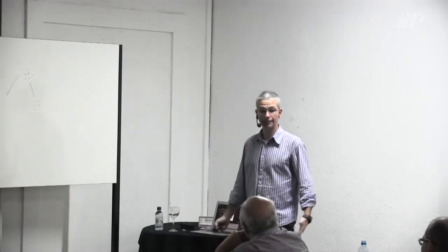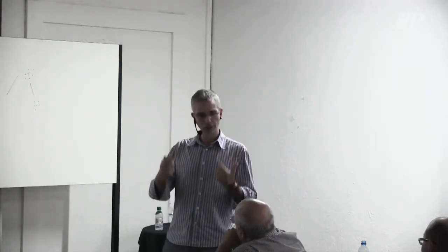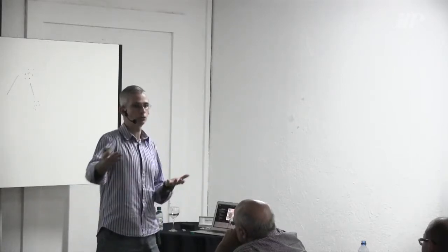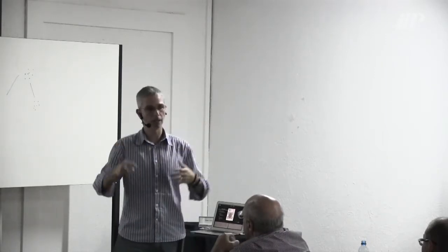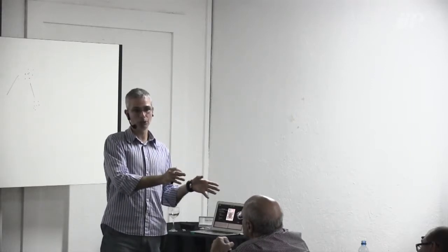Right. Well, depending on how you encode phase, 1.5 Tesla is already capable of inducing currents in peripheral nerves. So it's a technology that's moving in parallel to the increase of the magnetic field in order not to induce peripheral nerve or brain stimulation. What I'm saying is that at 1.5 Tesla, depending on the strategy that you use, you are already going to induce peripheral nerve stimulation.